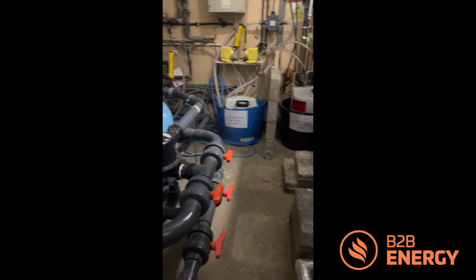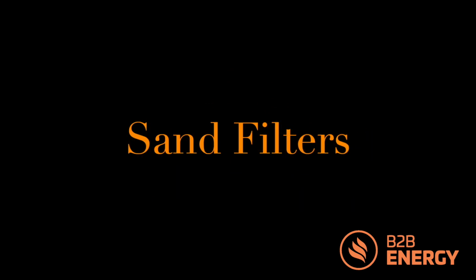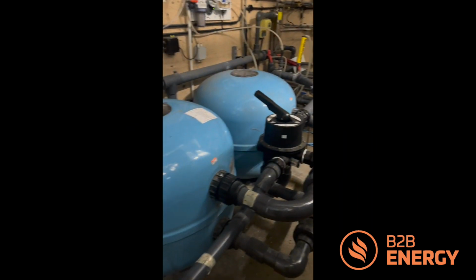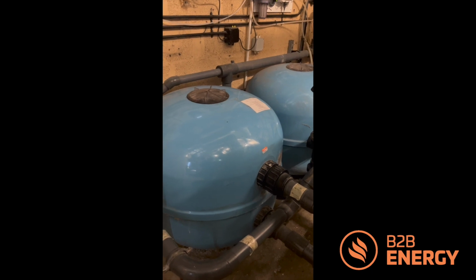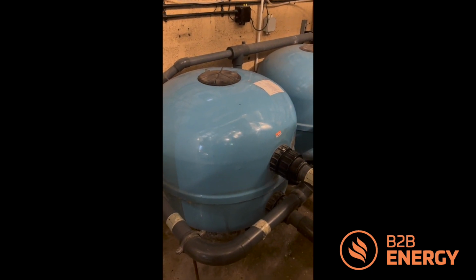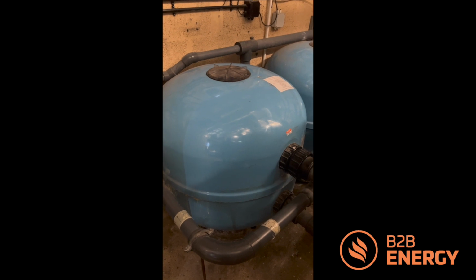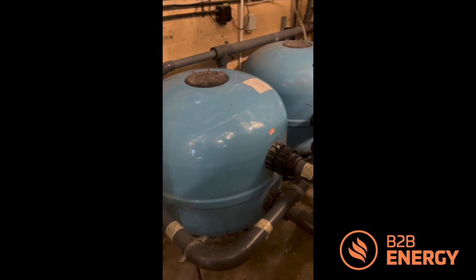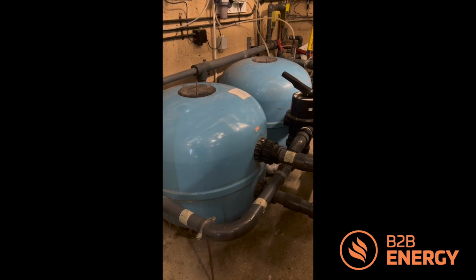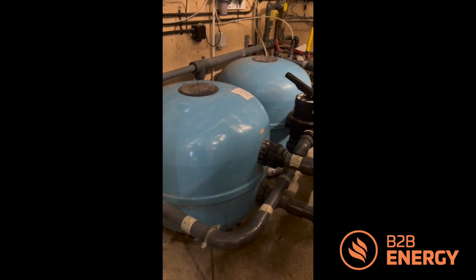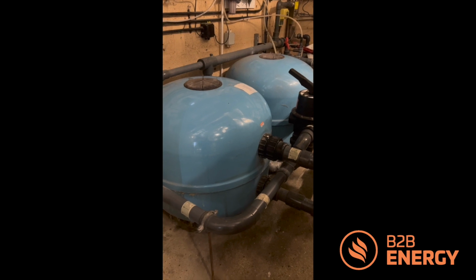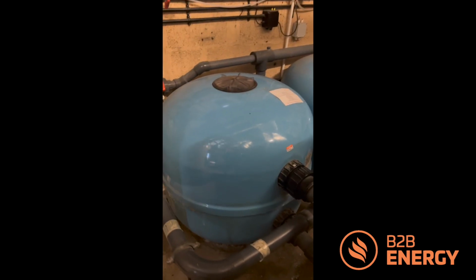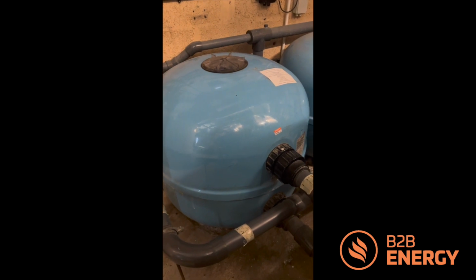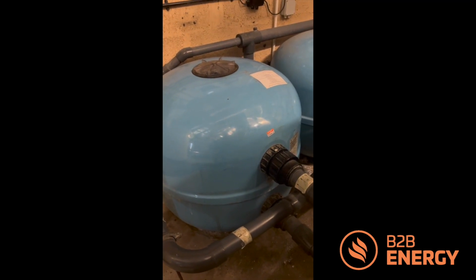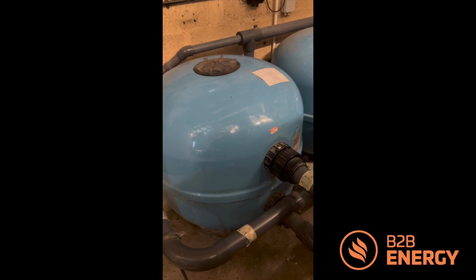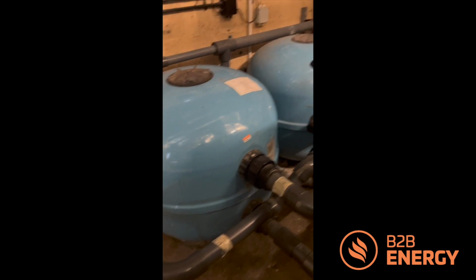These are the sand filters. These sand filters provide filtration on the swimming pool, and regarding that, they would be backwashed because obviously we need to keep that sand clean and not make it cake up. Regarding the water, after a period of time that will start to cake and clog together, so we'd expect these to be backwashed probably every other day and extending out, and it does depend on how many people we have and the volume of people going through the swimming pool.